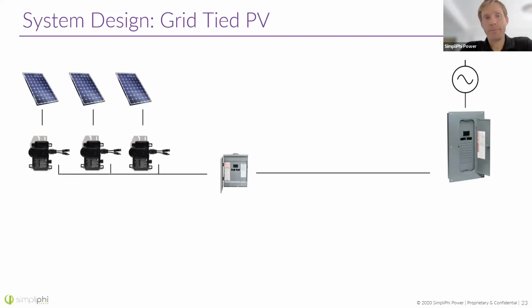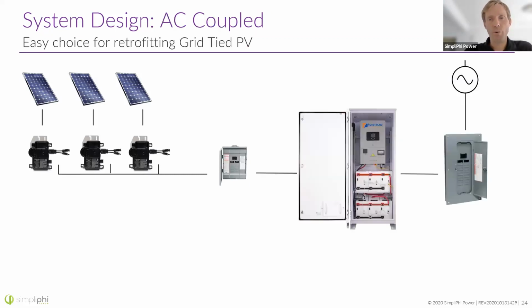So let's look at an example. This is just a simple string or grid tied PV array. We've got IQ7 pluses, looks like they're attached to solar panels, and those are producing 240 volts of AC power, and that's coming into a loads panel and then being fed back to the main service panel and into the grid. We want to add battery backup to that, and the same goes with a string inverter. We're looking at trying to retrofit this array, and in order to be able to use that AC power, it's like charging from a generator. We need an inverter to be able to take that power in and feed it back to the batteries.